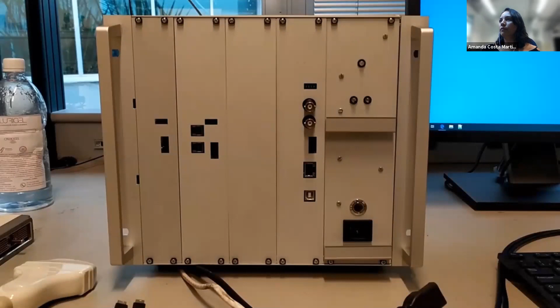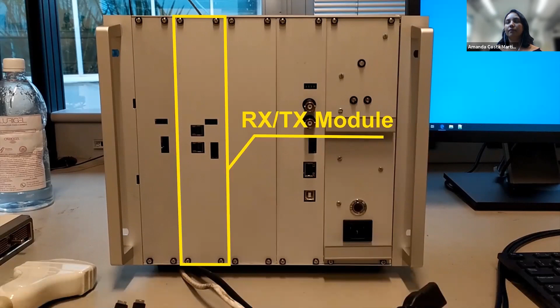The source module is responsible for AC power input and DC power distribution for the entire platform. The sync module receives configuration files and distributes them to other boards. Reception and transmission modules are where all components that make up the 64 channels are located. The MUX and transducer module has the components that make the multiplexing when necessary, and the connector for the transducer. Now, let's run the ultrasound imaging software on the platform's PC. Note that the generated image will be directly related to the chosen configuration file.